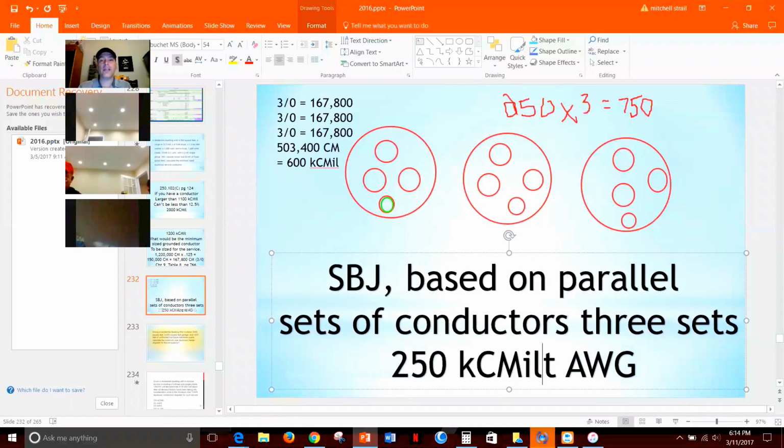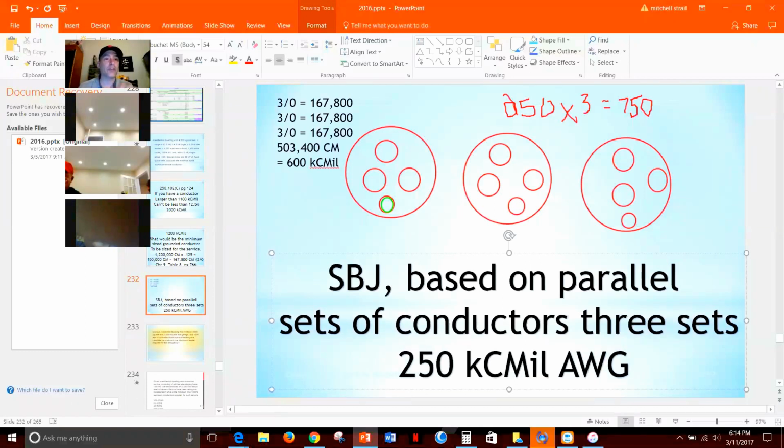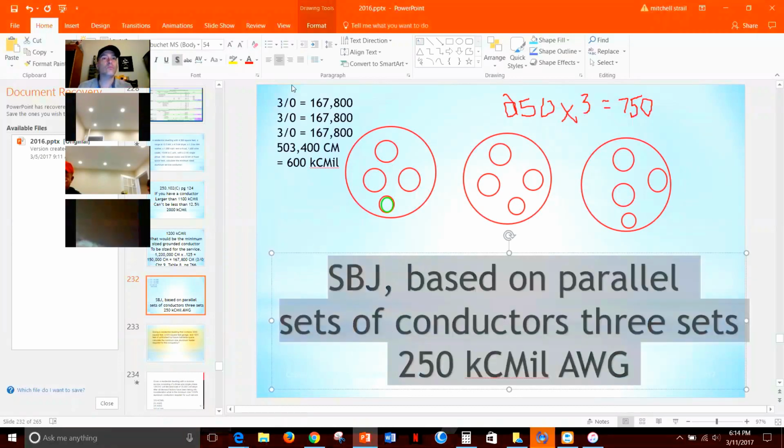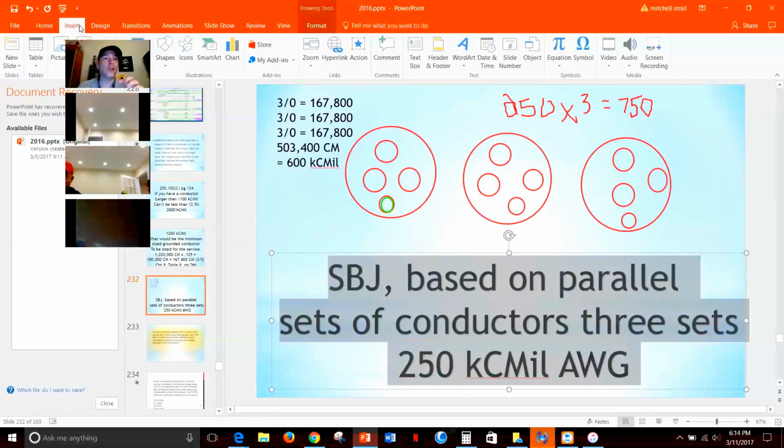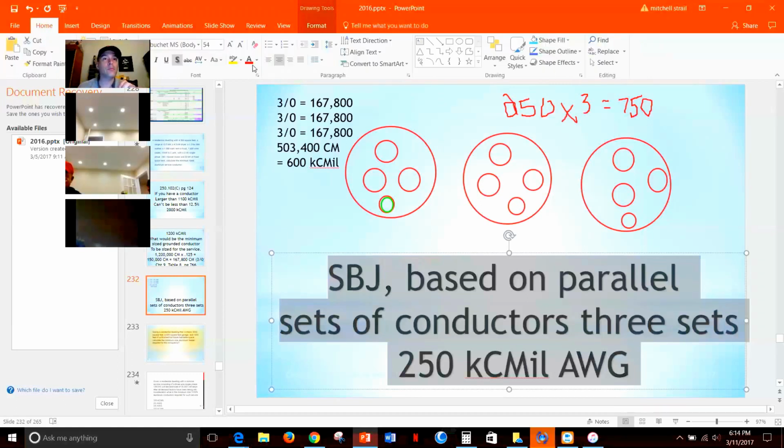If you look down at the bottom, remember that note 1 on that table has that 12.5% business, right? It's real similar to the other table because it first tells you to do the same fuzzy math. You have to take all 3 phase conductors, all the 3 hots, and add those up first, and then take 12.5% of the wire size that you came up with. You just have to add one wire in each pipe. Does that make sense?